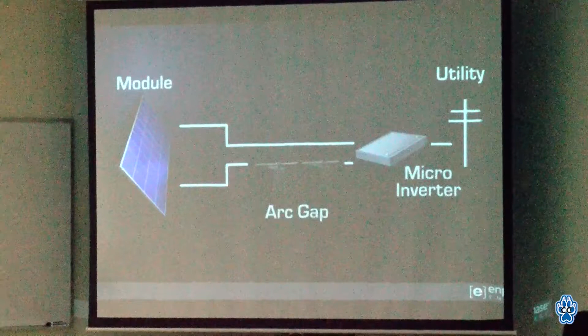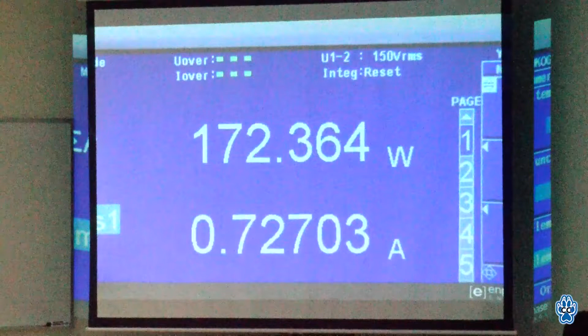The second case illustrates a microinverter scenario. The microinverter is exporting 170 watts to the grid. As you can see from this scenario, only the smallest of arcs is visible. Did you see it? For a very brief moment, it's just a little spark. The nature of a microinverter is that the arc is self-extinguishing.